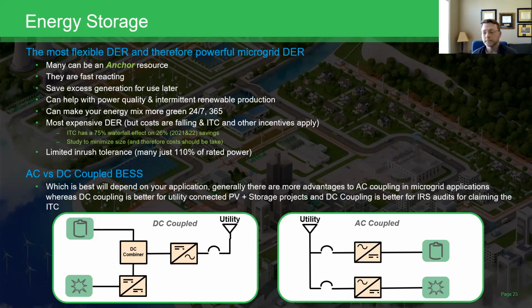One other potential drawback is that they have a limited tolerance for inrush. Many of you may not be familiar with inrush currents, but there are certain types of loads, going back to why it's very important to categorize the loads you have at your facility. There are certain loads out there, like a motor load, that has a very quick spike of power draw. And so maybe a load is typically 100 amps, but during this momentary inrush, it might be 600 or 1200 amps. And if your battery system power isn't rated to handle that, you could experience problems.